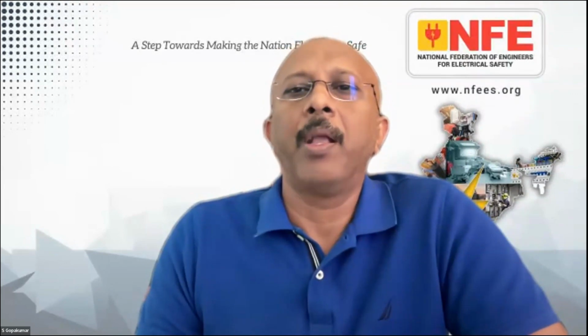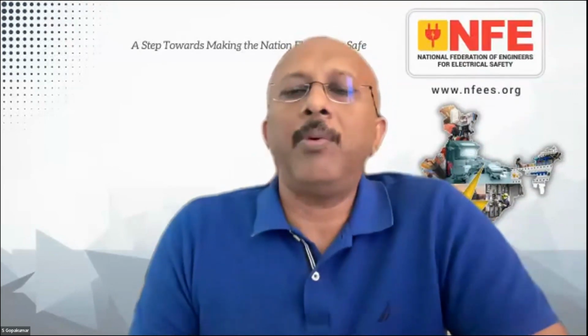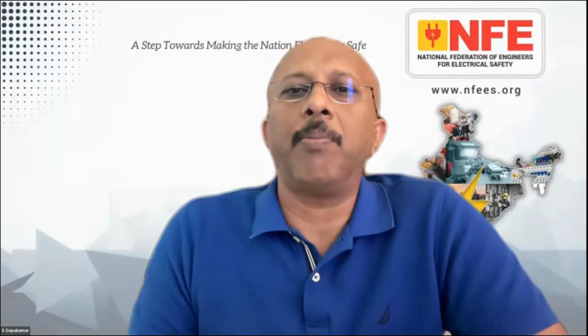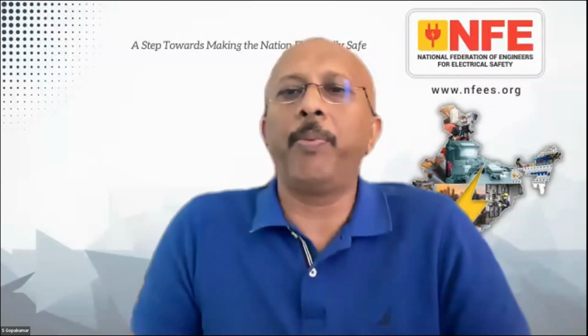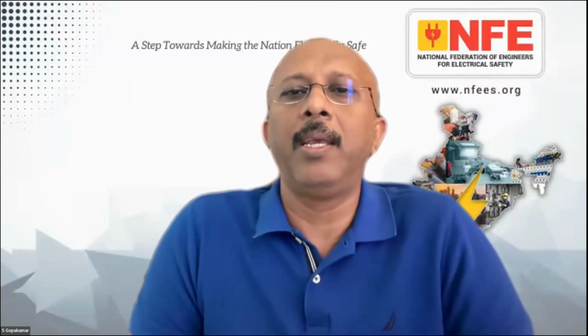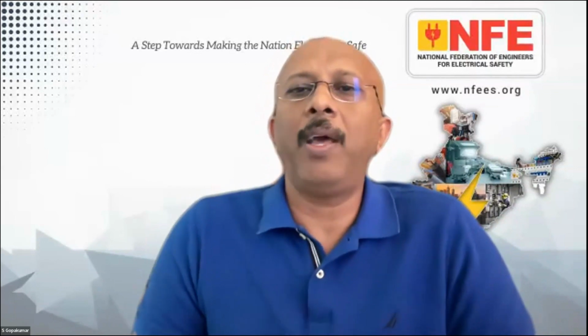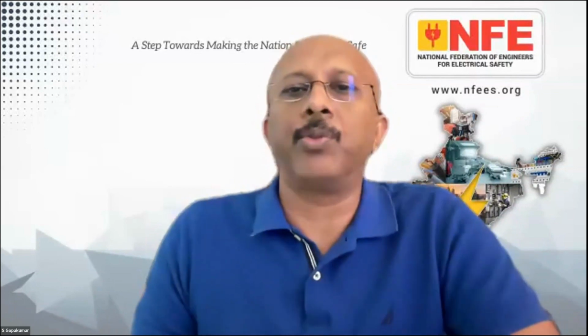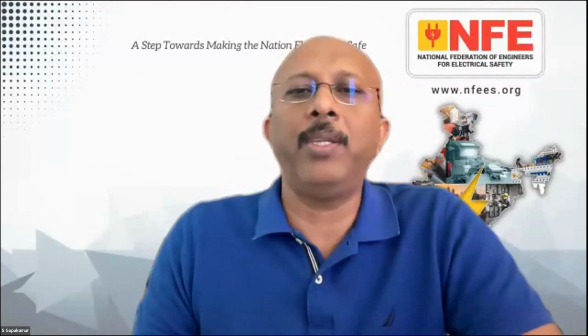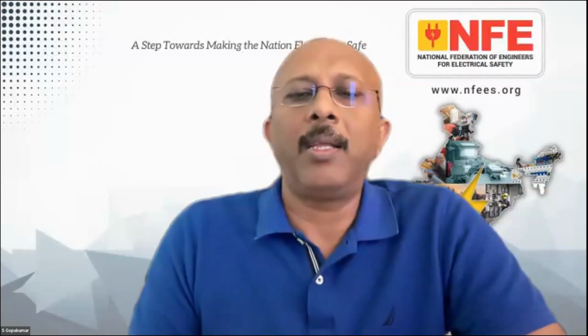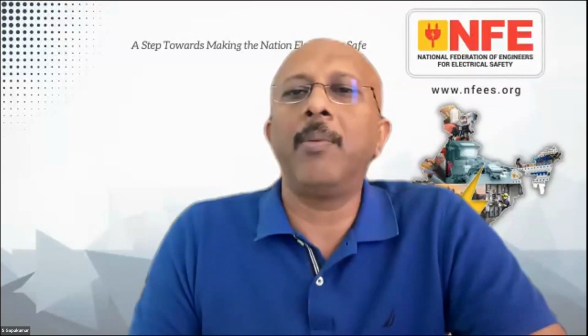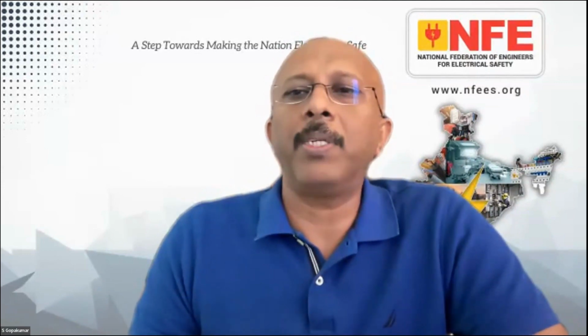Very simple. So now there is another question from Mr. Prafulla. Recommended values of loop impedance for MCB are given. Kindly give the same value for DIN type GL fuse. Okay, Mr. Prafulla, the better way is you can get the disconnection curve of the protective device which you are referring to, and you can get that information from the manufacturer's catalog.